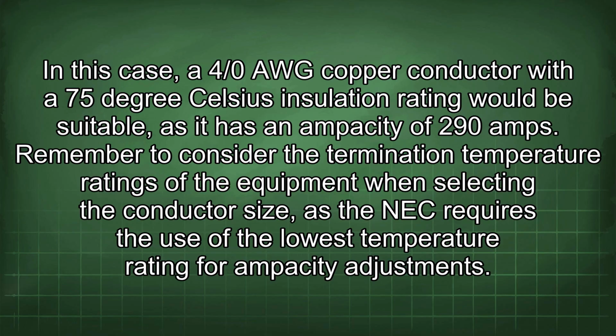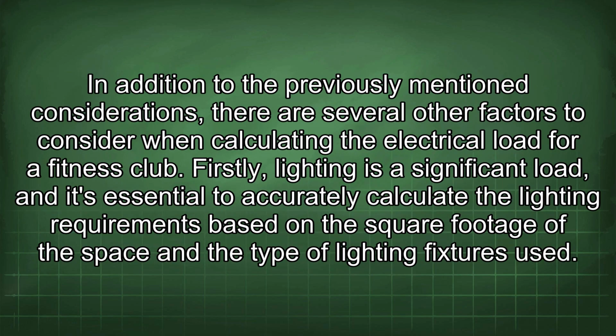Remember to consider the termination temperature ratings of the equipment when selecting the conductor size, as the NEC requires the use of the lowest temperature rating for ampacity adjustment. In addition to the previously mentioned considerations, there are several other factors to consider when calculating the electrical load for a fitness club. Firstly, lighting is a significant load, and it's essential to accurately calculate the lighting requirements based on the square footage of the space and the type of lighting fixtures used.